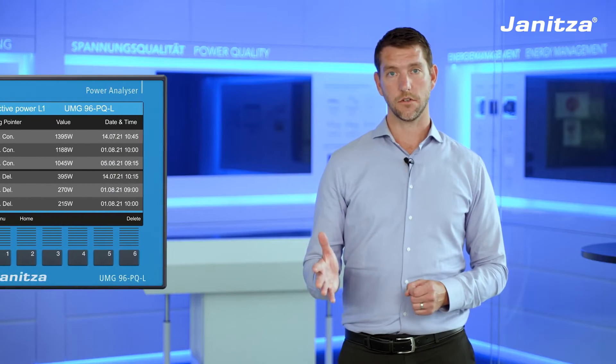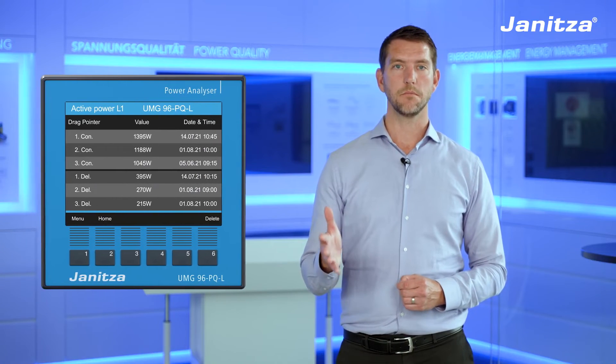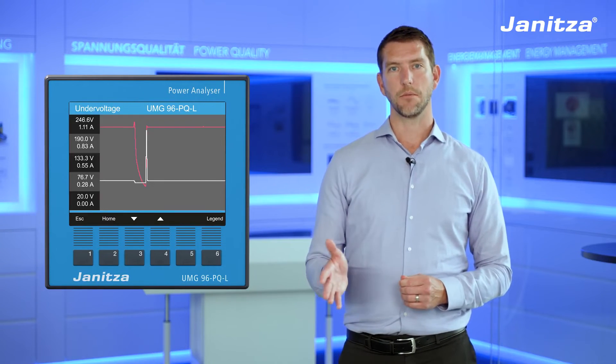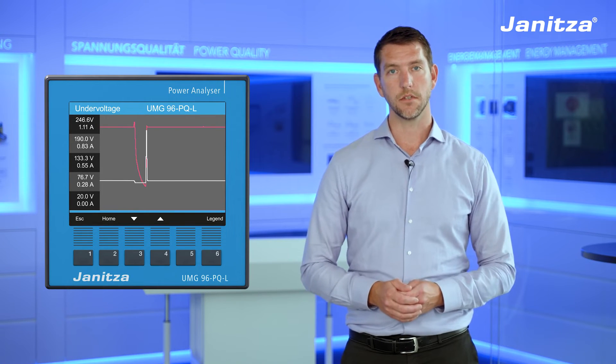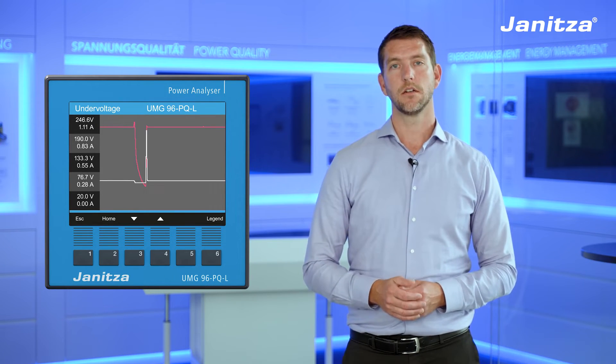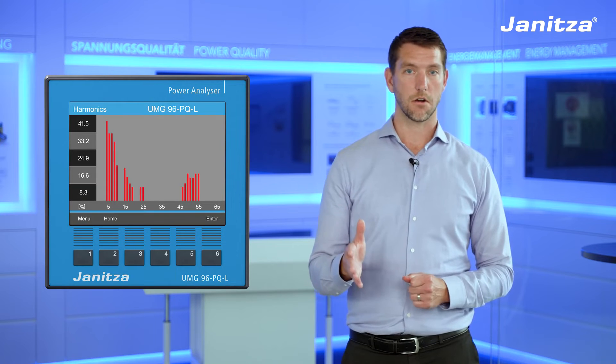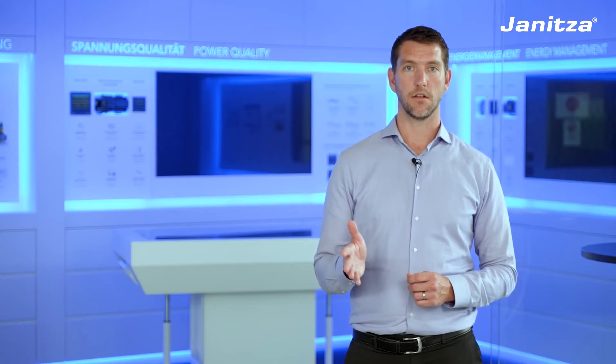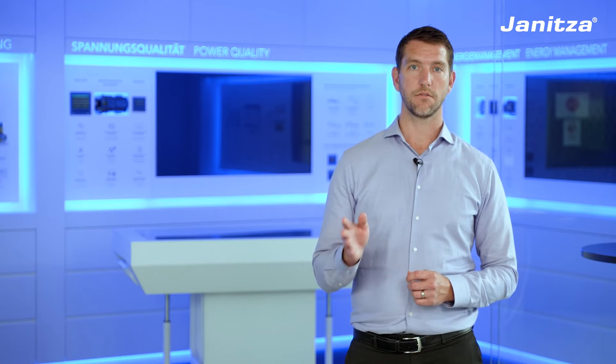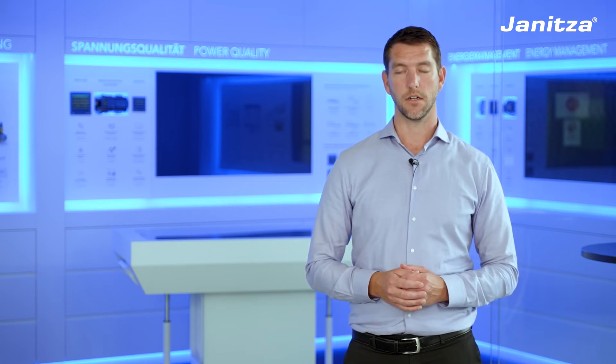For the advanced users, there is a peak demand indicator, event capturing when events are longer than 20 milliseconds, harmonic measurements up to the 65th, and interharmonics. It has an EMC class B rating, which means it can be used in multiple industrial, commercial, and residential zones. The Ethernet interface allows up to five software applications to run in parallel.